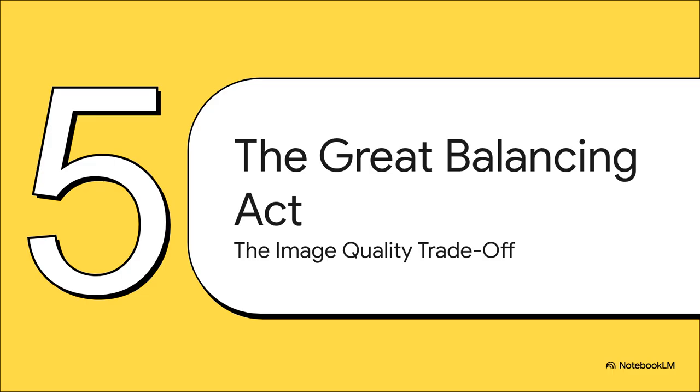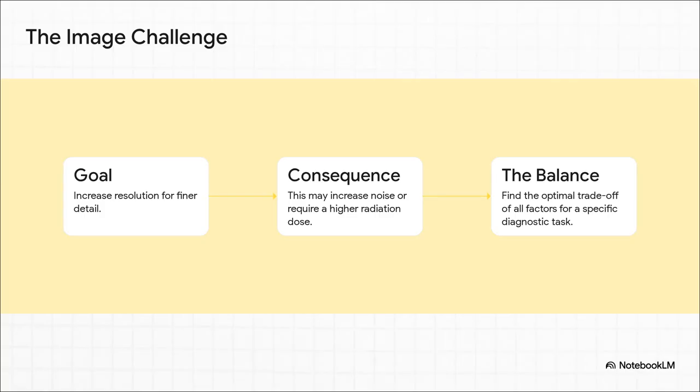Now let's put it all together and see how they interact in the real world. Because this is where the real balancing act begins. And this is the challenge they face every single day. Let's say your goal is to crank up the resolution to see more fine detail. Okay, great. But the consequence might be that you get more noise in your image. Or you might have to use a higher radiation dose, which comes with its own safety issues.